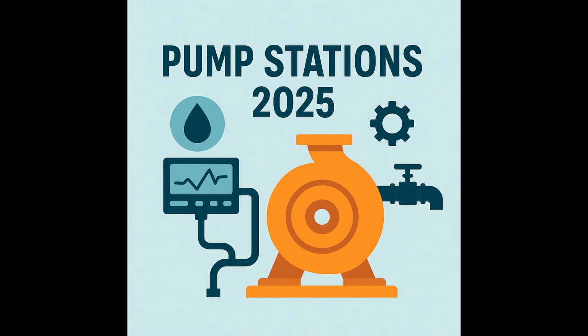We've talked about functional control, but what's the actual playbook for these smart systems, and maybe what's the brain that executes it all? Good question. The playbook is what we call the control narrative. This is a crucial written document, really, a specification that explains precisely how a pump station, or really any automated system, is supposed to operate. It details everything: start-stop conditions, maybe based on wet well levels or system pressure, how lead and lag pumps rotate to share the operating hours fairly, what conditions trigger an alarm, and all the critical fail-safes. It's essentially the blueprint before you even start programming the system.